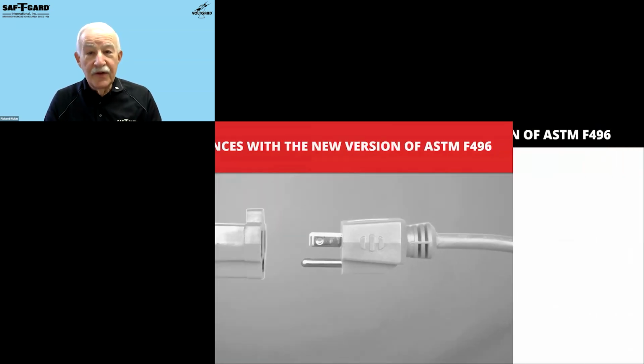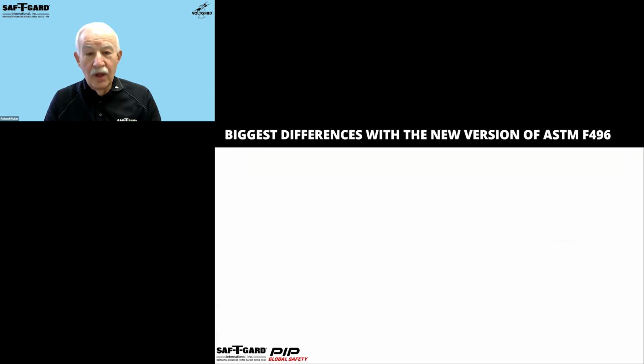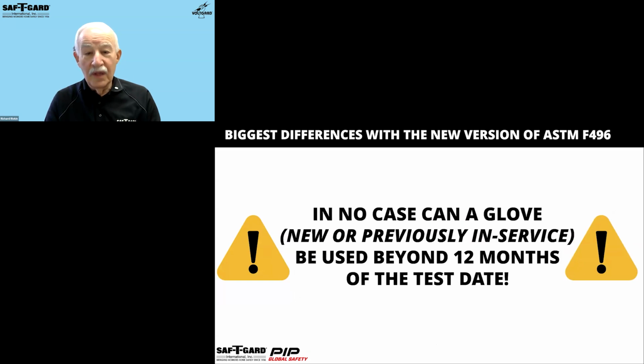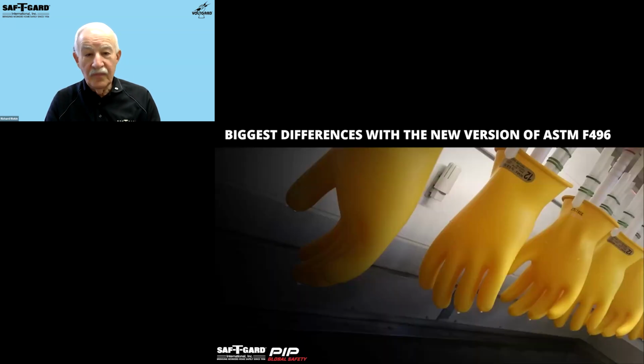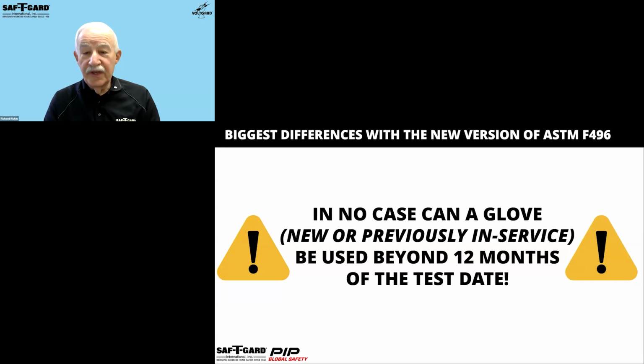So again, the biggest difference in the in-service standard, the most critical change, is the clear statement that in no case can a glove or sleeve be used beyond 12 months of the test date. With the addition of this section, the usage window for rubber insulating gloves is now more clearly defined. For example, if gloves are tested on January 1st and stored properly, they can be issued for any time during that calendar year. If issued in March, they can be used for up to 6 months, requiring retesting in September.